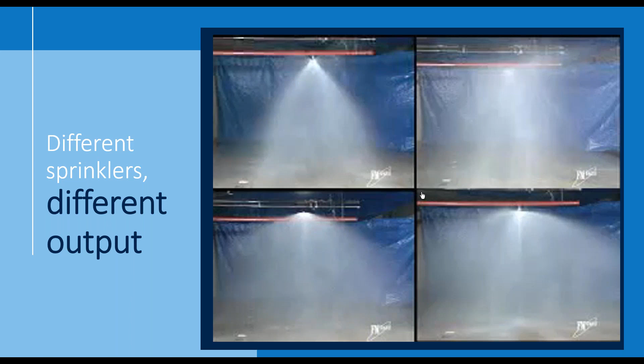Now, this was supposed to be a very nice video, and here it goes, of a real-time fire situation. We've set this up in a lab, a rather large lab, to show the difference between fire in one situation with sprinklers and one without. These are just boxes of plastic cups in cardboard cartons, a very small storage array. It's a real-time fire. What you'll see, fire likes to grow vertically in storage arrays in particular, and you see the fire has got to the top of the array in under a minute. People should be surprised by that. Fire in this type of commodity can go very quickly.